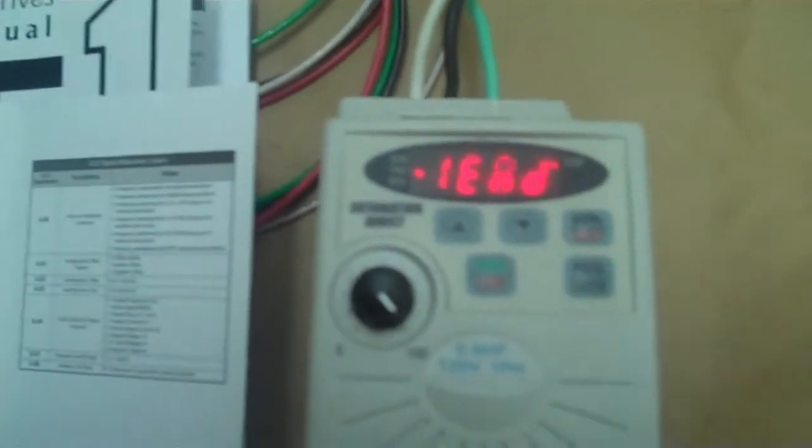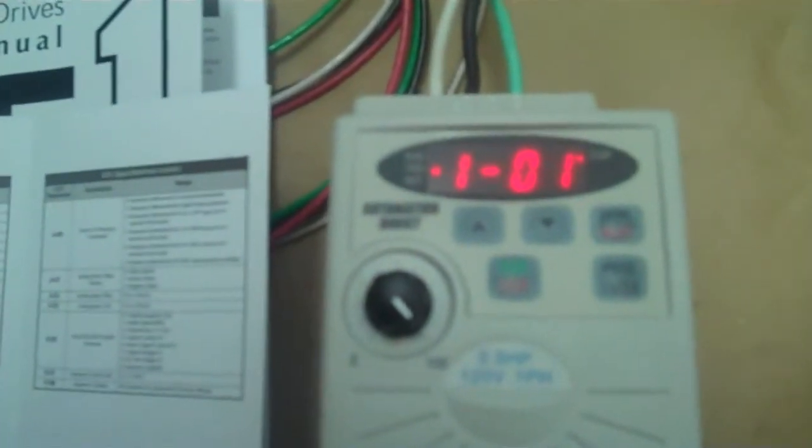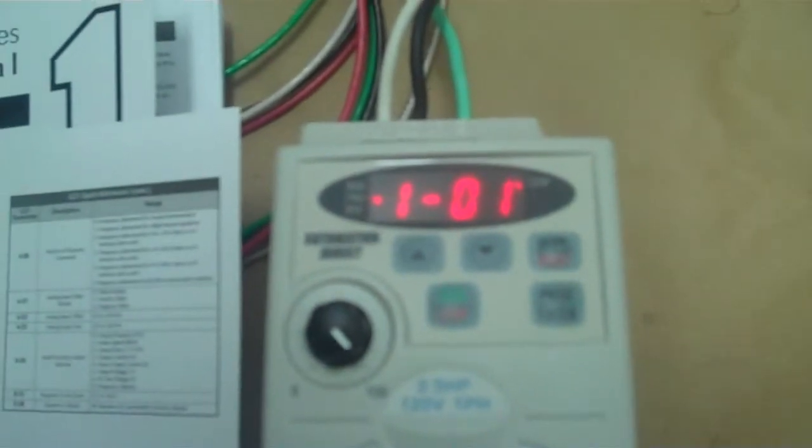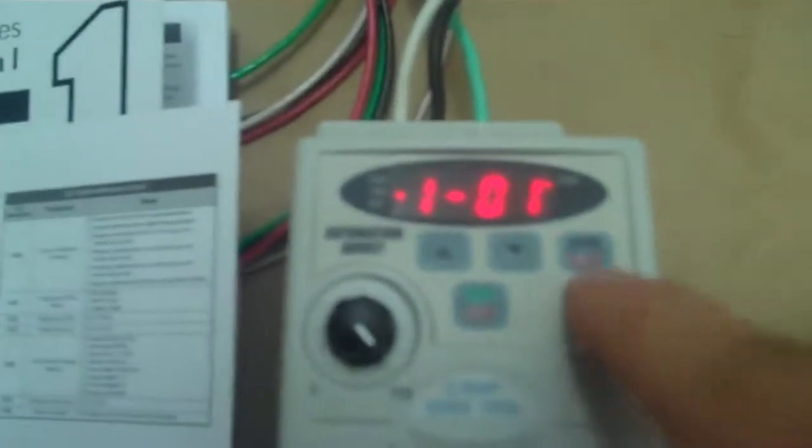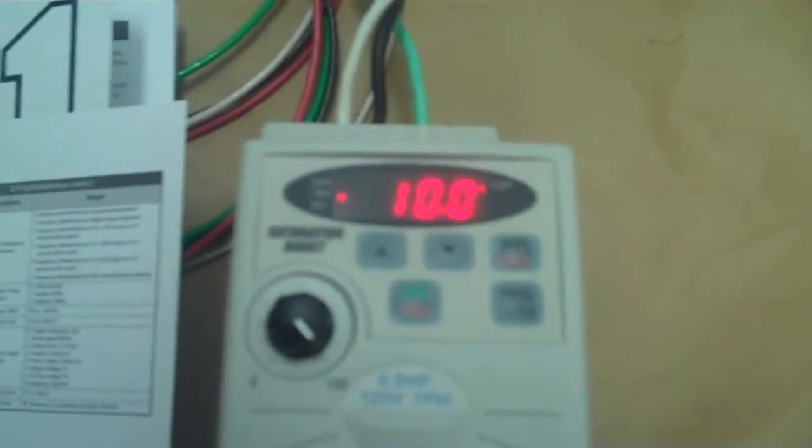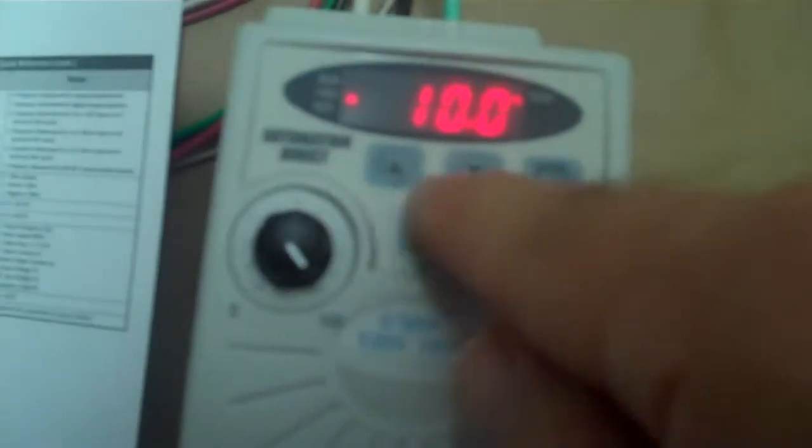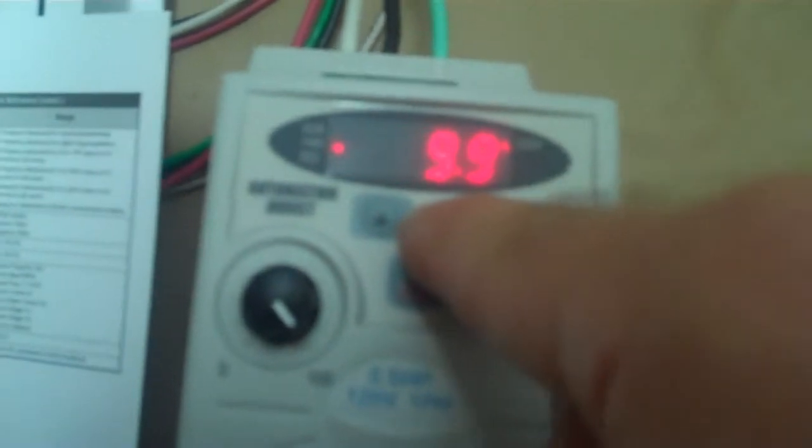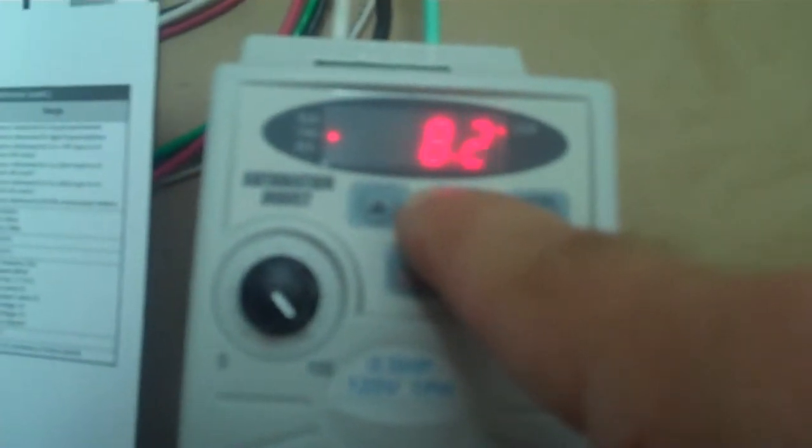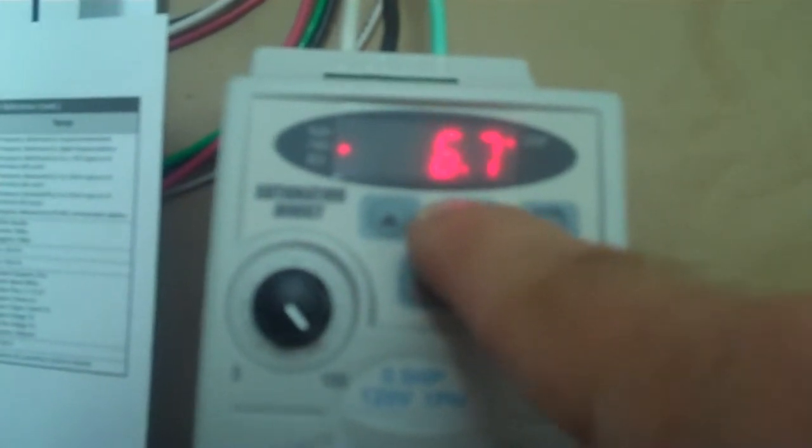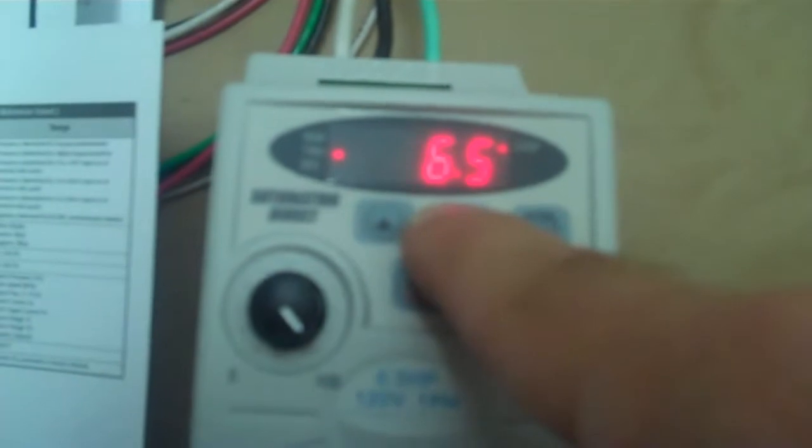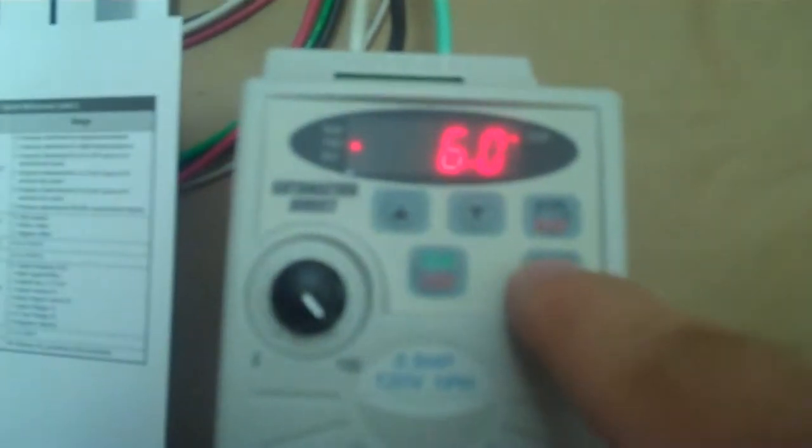Now we're going to go to one dash zero one which is acceleration time and it's set up to ten seconds. Now you can leave it at ten seconds if you're happy with that but I'm going to bring it down to be a little more exciting. We can do let's say six seconds. That's the speed it's going to take to get up to speed.